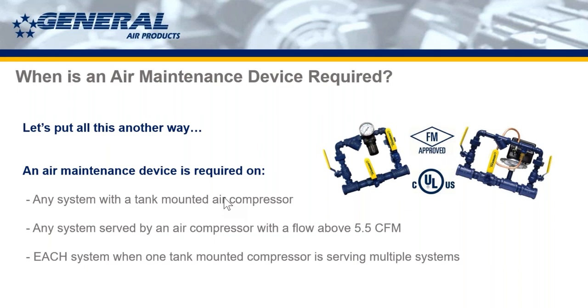So let's put this another way. An air maintenance device is again required on any system with a tank-mounted air compressor. So anytime you have a tank-mounted air compressor, you will need an AMD1 with an air regulator. Any system served by an air compressor with a flow above 5.5 CFM, you need an air maintenance device. If you're using a riser-mounted air compressor, in that instance you need an air maintenance device. But a riser-mounted compressor with an air maintenance device is not typically a good idea. You get a lot of short cycling because there's a lot of volume and pressure gets built up just in the small amount of piping between the two. And as that pressure bleeds off, the compressor runs for short amounts of time to catch up with the loss of pressure in the run between the compressor and the AMD.